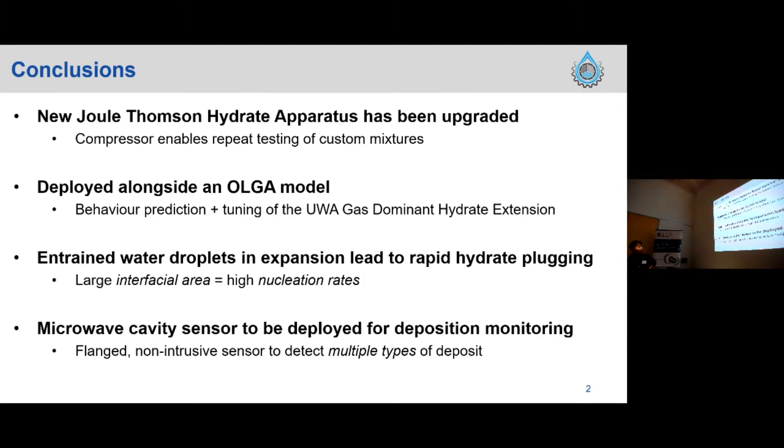And last, Matt will introduce you to the microwave cavity sensor for deposition monitoring. The beauty of this technology is it's non-intrusive and it can detect multiple solids like hydrate, ice, scale, and wax.